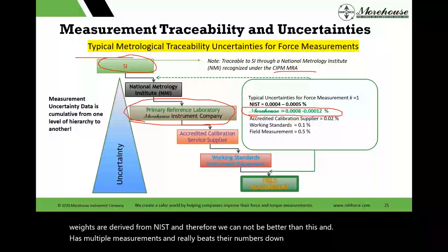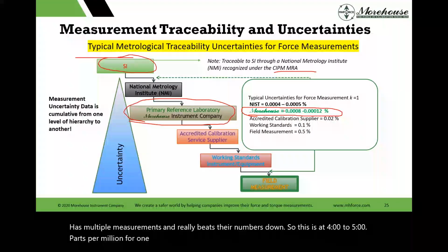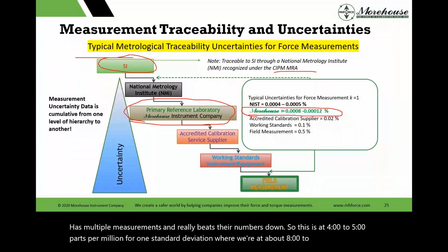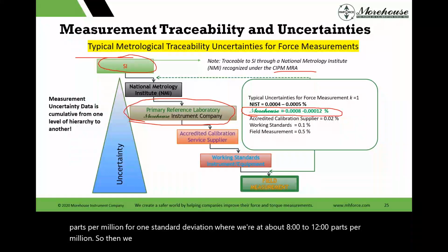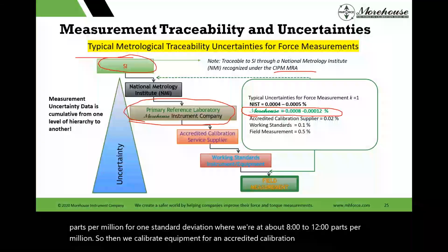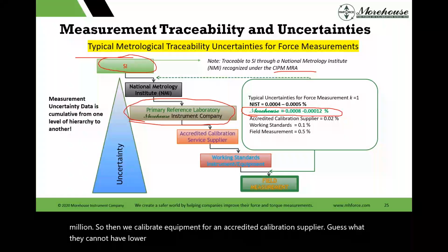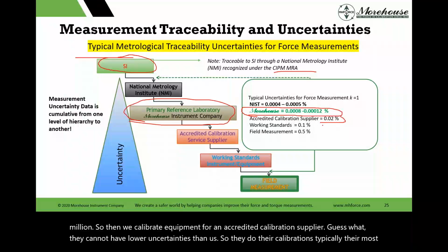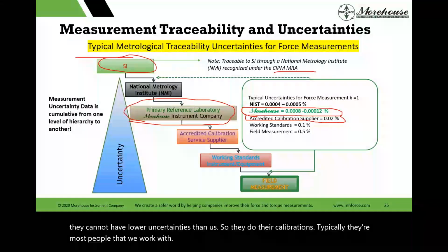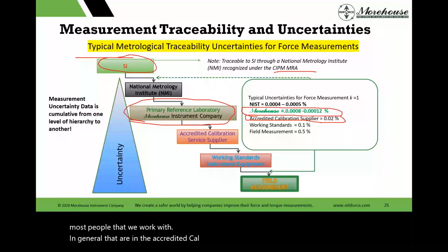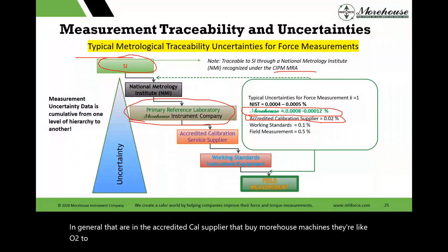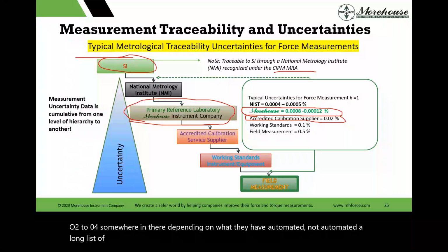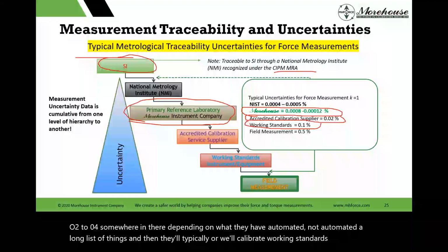So NIST is at 4 to 5 parts per million for one standard deviation, where we're at about 8 to 12 parts per million. So then we calibrate equipment for an accredited calibration supplier. Guess what? They cannot have lower uncertainties than us. So they do their calibrations. Most people that we work with in the accredited cal supplier space that buy Morehouse machines are at like 0.02 to 0.04, somewhere in there, depending on what they have, automated, not automated, a long list of things. And then we'll calibrate working standards, dynamometers, force gauges, all the other stuff.